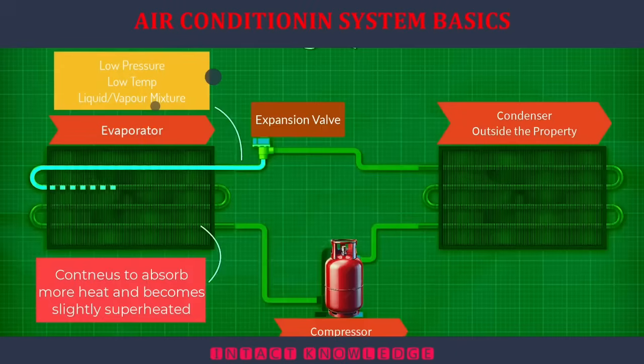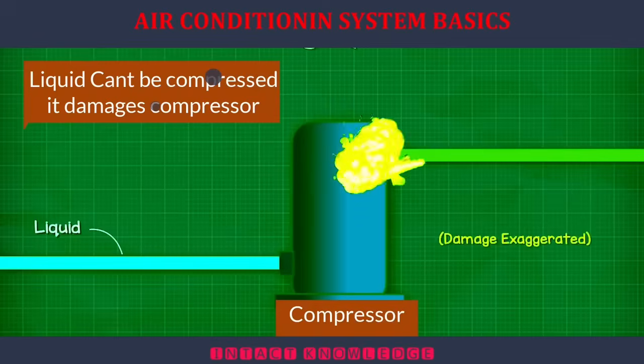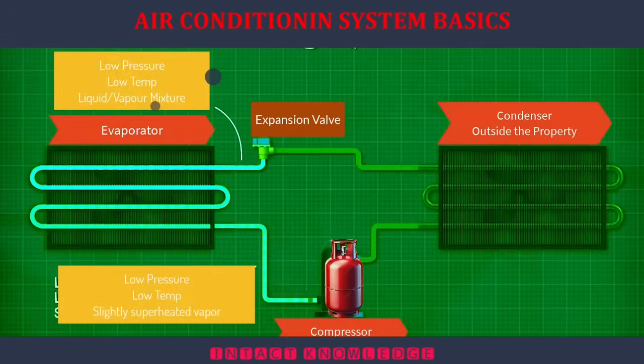The refrigerant continues to travel through the evaporator, picking up more heat, which boils it further until it becomes slightly superheated. This basically means it's now completely gas and doesn't contain any droplets of liquid refrigerant. Liquid damages the compressor, so we want to ensure it can't reach the compressor. The compressor sucks in the refrigerant, which is leaving the evaporator as a low-pressure, low-temperature, slightly superheated vapor.